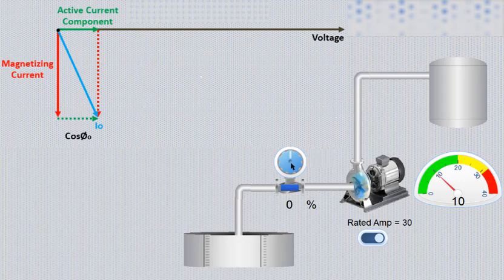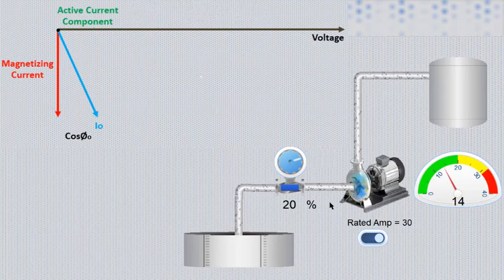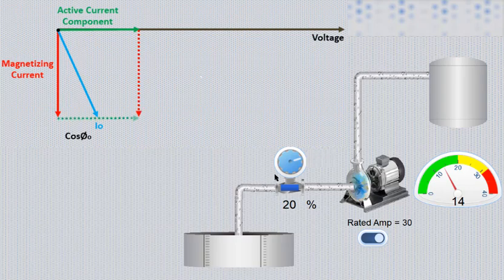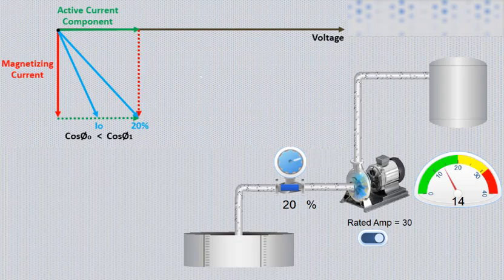Now, load is increased 20 percent by opening suction valve to 20 percent. As this load is active part of power, this tends to increase the active component of current, while magnetizing component will remain same. The resultant vector of current will move towards voltages causing improved power factor.